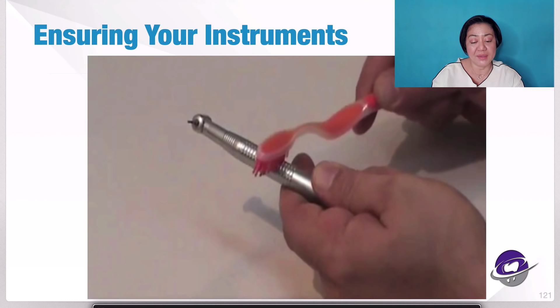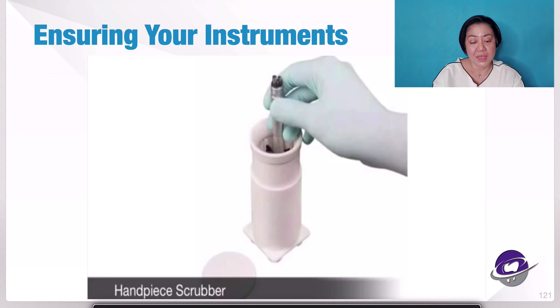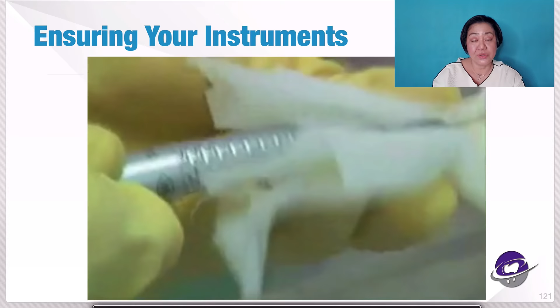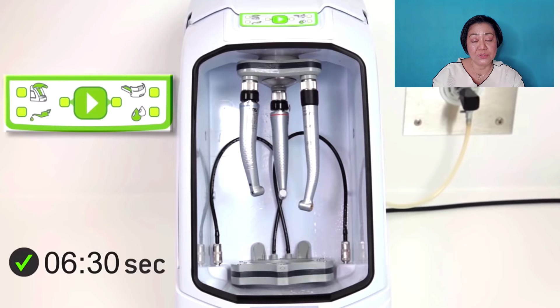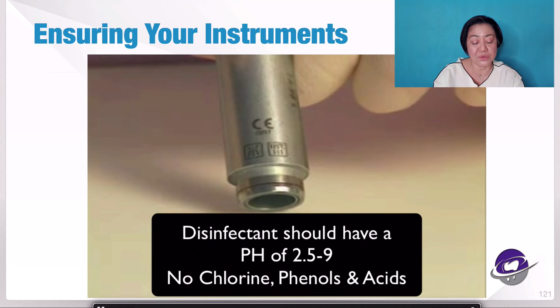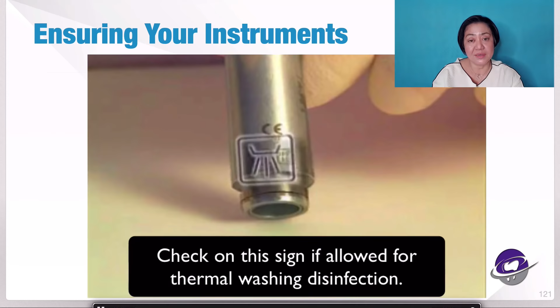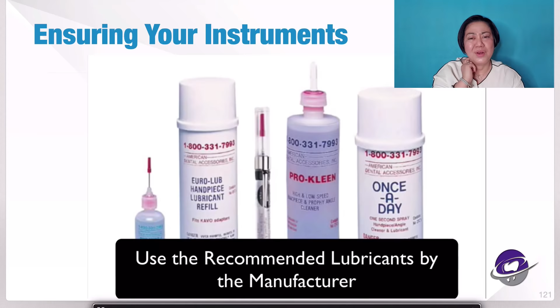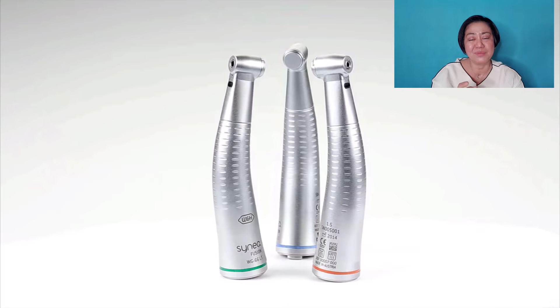Now, this is how you clean the handpiece. You can also use this scrubber to remove the grime. But again, may I remind everyone that, yes, here, this is how you disinfect it. You have to disinfect it all the time before you autoclave it. And please do not use chlorine, phenols, and acids because these can damage your handpiece. So you do not soak it in water or any chemical disinfectants. And then always, again, read the manufacturer's instructions. Now, when you lubricate it, please make sure that the oil you are using is the manufacturer's recommendation. Because a long time ago when I was starting in my practice, I used to lubricate my handpiece with this motor oil.